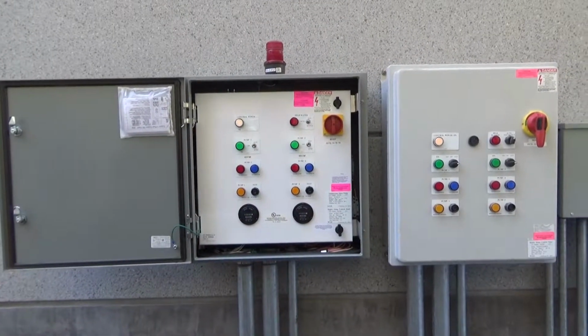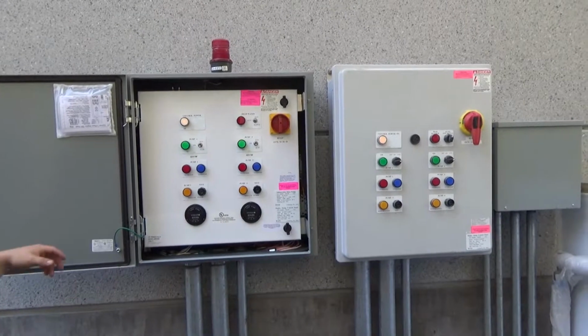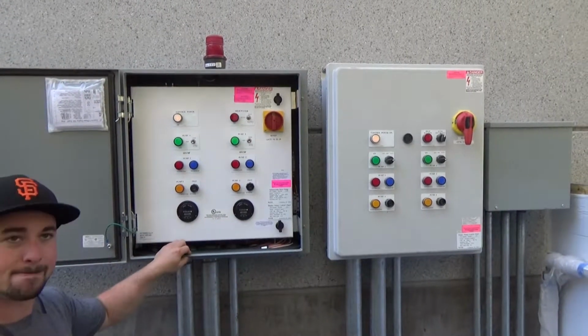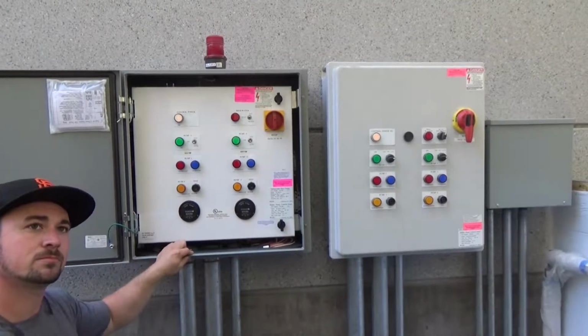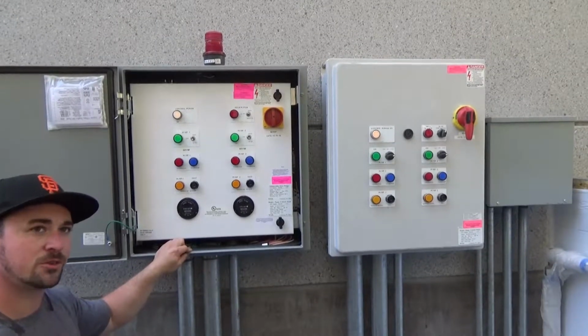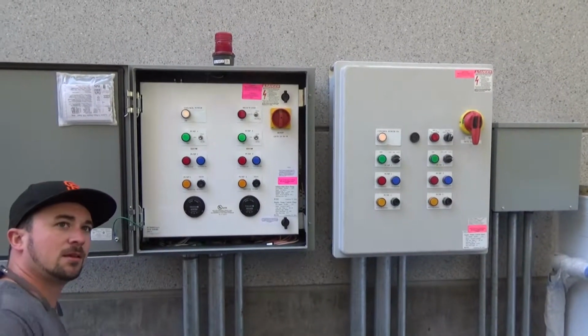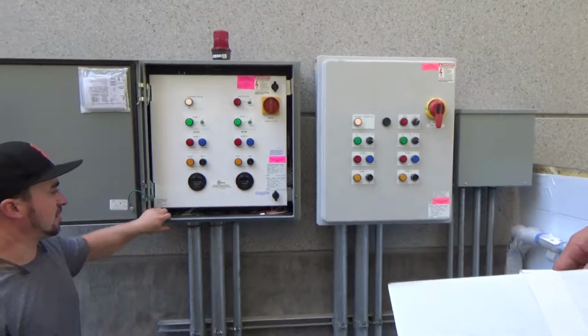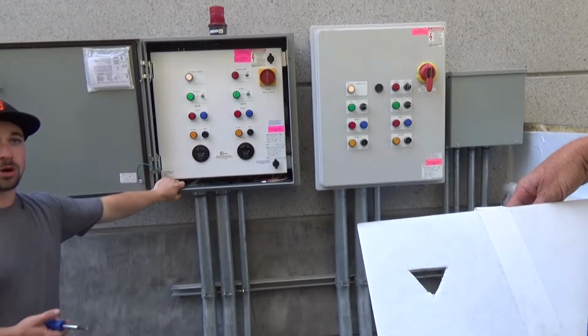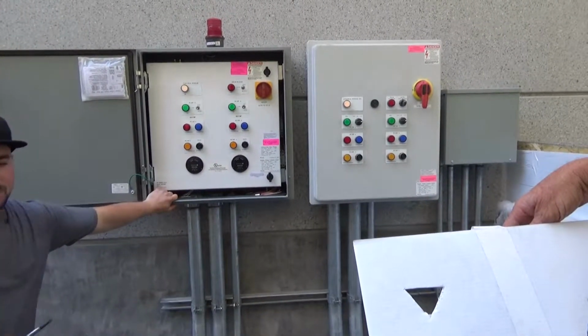Any questions? The over temp, would that happen if, say, a float valve sticks and the pump continues to run and there's no more water in the sump? Correct. So it would kick at that point as well, because you're just sitting there running dry, getting hot. The way those motors are cooled down is via the water in that pit. And the one thing about those pumps is that you always want to keep that volute submerged.